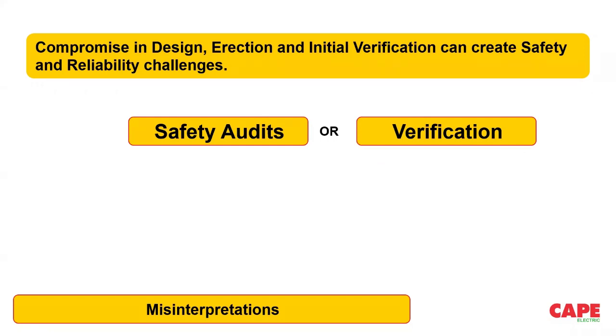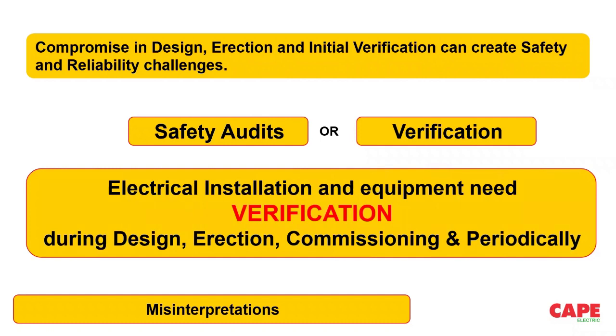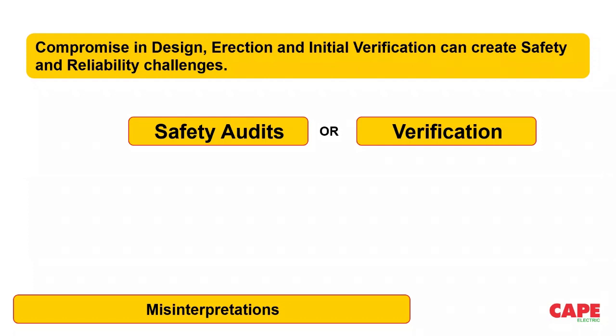The difference between audit and verification is that in a verification, you are supposed to inspect and test all the points. In an audit, not all the points, according to your convenience. So the auditor can decide the amount of things he is supposed to do, whereas in a verification, he cannot make that decision. He has to go as per the standard, because with electrical or fire installations, we are talking about the safety of people. Say, for example, in an ISO 9001 audit, if you find 2 non-compliances, you can rectify them later on. Whereas in a safety audit, if you find 2 non-compliances and try to rectify them after some time, within this time there can be an accident.